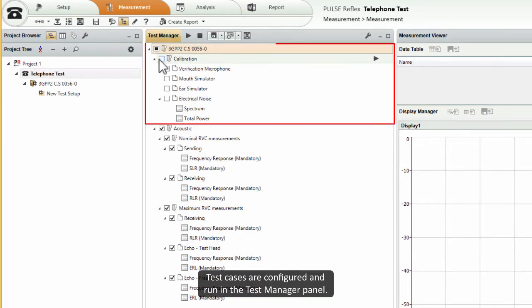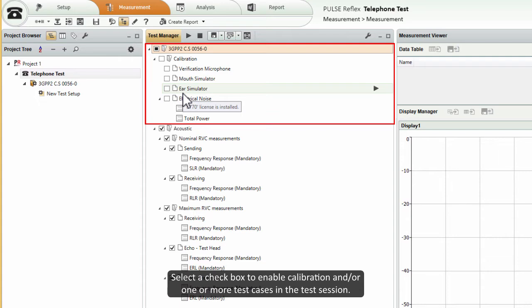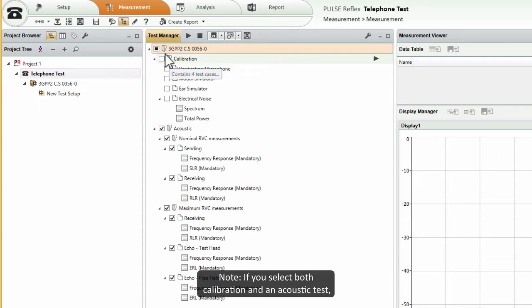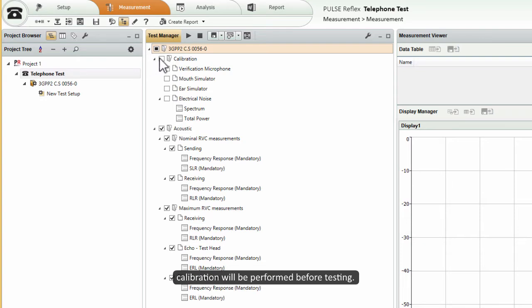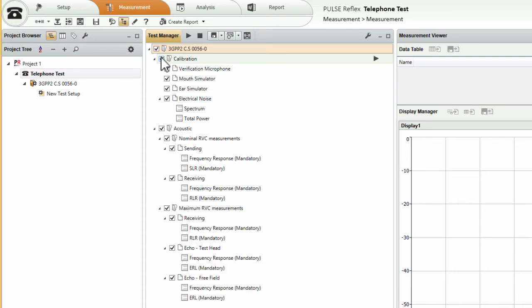Test cases are configured and run in the Test Manager panel. Select a check box to enable calibration and or one or more test cases in the test session. If you select both calibration and an acoustic test, calibration will be performed before testing. Calibration will normally be valid until the test environment changes.